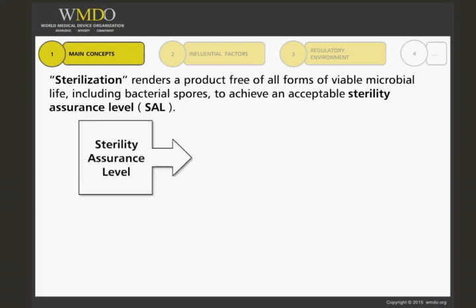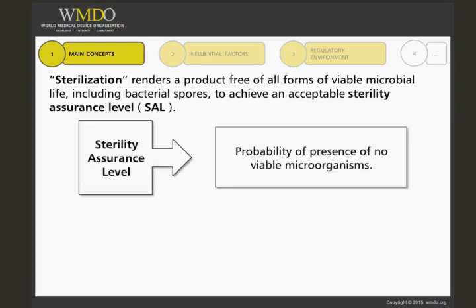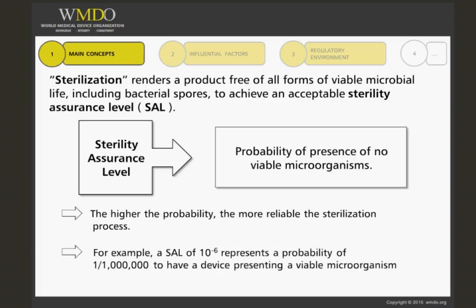Sterilization is about rendering a product free of viable microorganisms. Regarding sterilization, 'free' means a probability of having no viable microorganisms, and this probability is never 100%. For this reason, the standard introduces the notion of the Sterility Assurance Level, or SAL. The SAL of a sterilization process is the final probability of having a viable microorganism on a product. For example, an SAL of 10 to the minus sixth represents a probability of having one viable microorganism out of one million products treated.